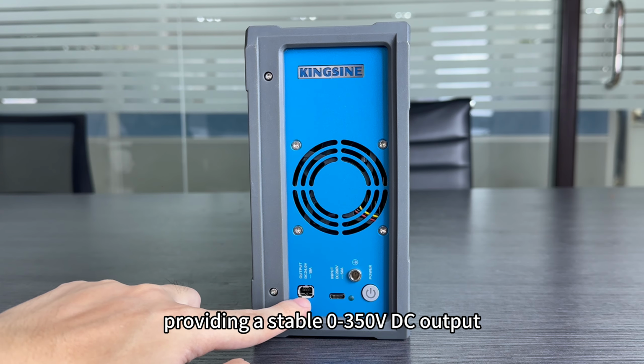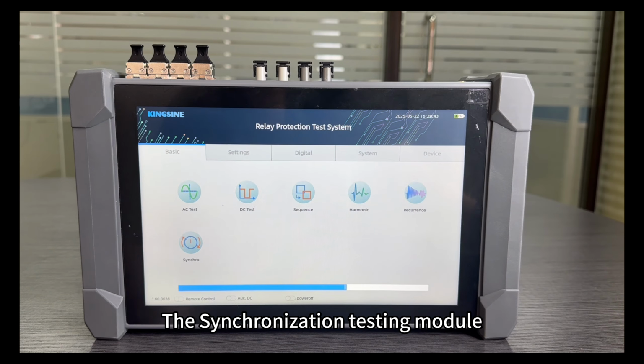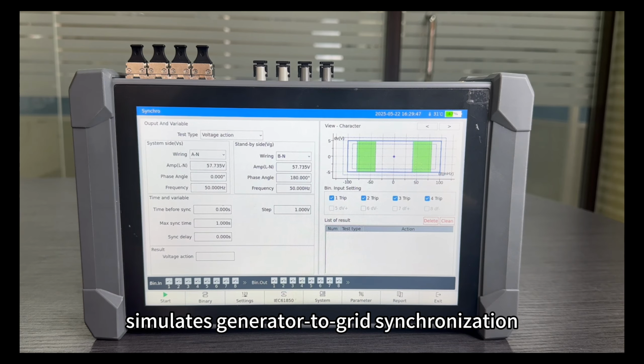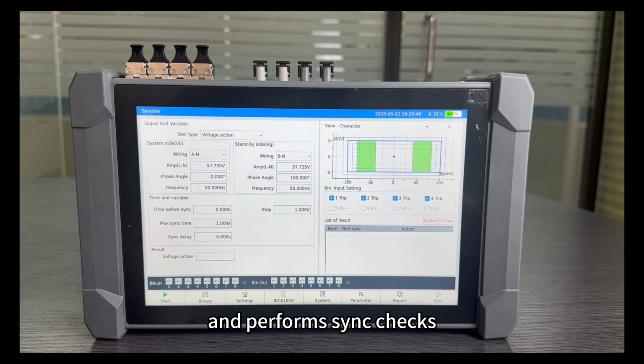The harmonic testing module allows users to set the base wave and 6 harmonic components. After configuration, all groups output simultaneously, and the waveform preview shows harmonic content. Results are listed with action values and times. The recurrent function allows the device to replay the Comtrade fault waveforms repeatedly. The synchronization testing module simulates generator-to-grid synchronization and performs sync checks.